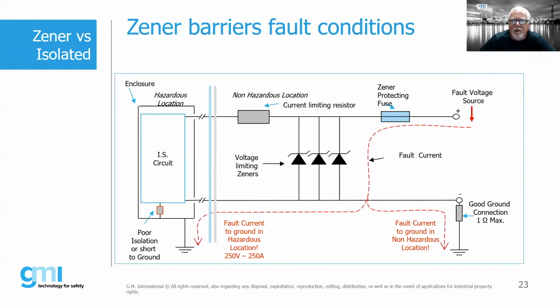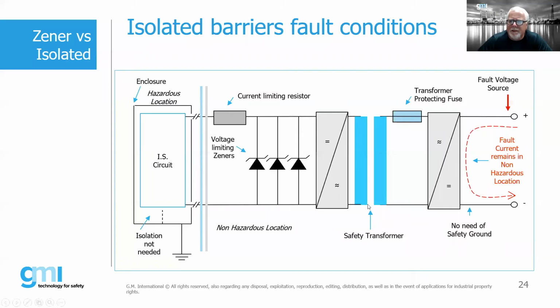So when we have a Zener barrier under a fault condition, as I mentioned in the other slide, this fault could potentially come down. Again, if we don't have a good ground connection, it could travel into the hazardous area. Or if we have this ground tied in over here, we could potentially have a fault condition in the hazardous area that allows a lot more current into it, potentially arcing and sparking, thereby resulting in a bang. We don't want to see that. In a similar scenario using a galvanically isolated barrier, the fault condition stays within the non-hazardous area, so it's not transmitted through the safety transformer.